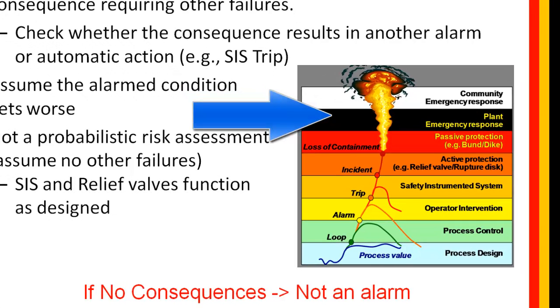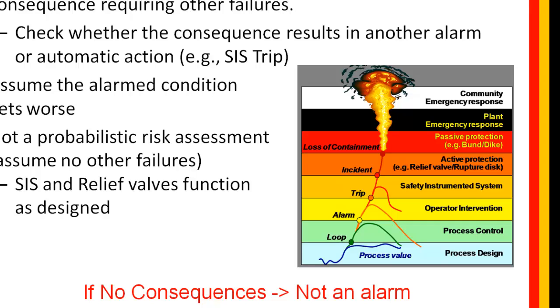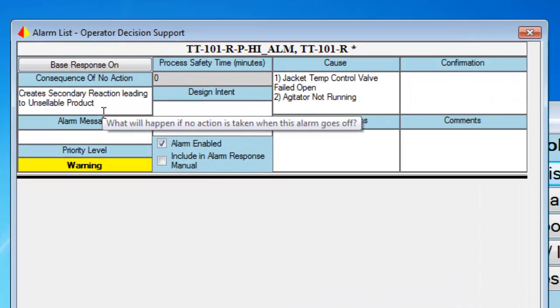As shown in the figure, the ultimate consequence would be a chemical release or explosion, while the direct consequence of the operator failing to respond to the alarm would be the trip of the safety instrumented system. Another important point about consequences: if you can't define what the consequence is, then there is probably no need for the alarm. Also, if the only consequence of the operator failing to respond is the creation of another alarm, then chances are both alarms are not necessary.